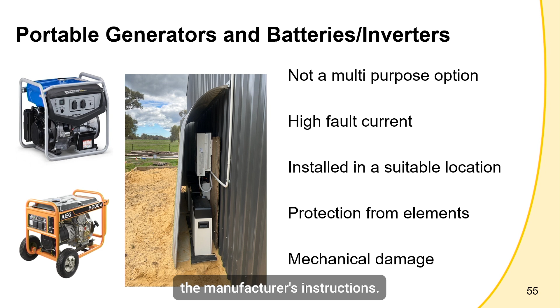Therefore, they must be installed in a suitable location, not like the one in this image. They've got to be properly protected from mechanical damage. Much of the mobile machinery on your properties doesn't have great parking capabilities, so backing into an unprotected battery system could be catastrophic. The fires are extremely difficult to extinguish, and they also emit toxic gases. As with all plant and electrical equipment, you must ensure that it's installed, operated, and maintained as per the manufacturer's instructions.